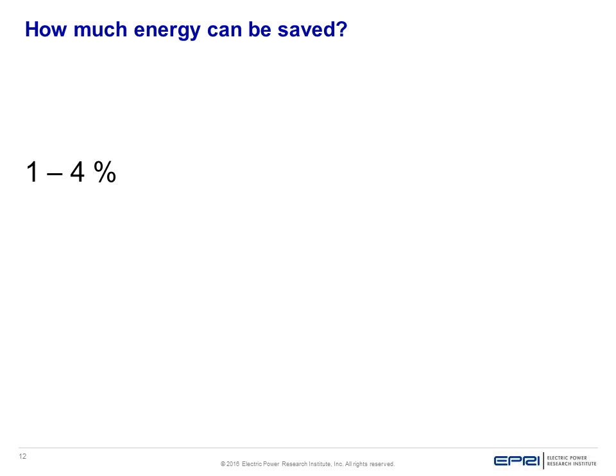The PNNL report did a nationwide survey and estimate - they figured that if you did it everywhere in the U.S., you're looking at something like a 3% reduction. Their estimate, if you just did it on high-value feeders - the easiest ones, where you get the most benefit - you could still get 2.4% energy savings across the board in the U.S. So there's quite a lot of opportunity there, and as an energy efficiency program it generally rates very high on cost benefits. It doesn't take much investment to make significant gains from CVR or VVO optimization.